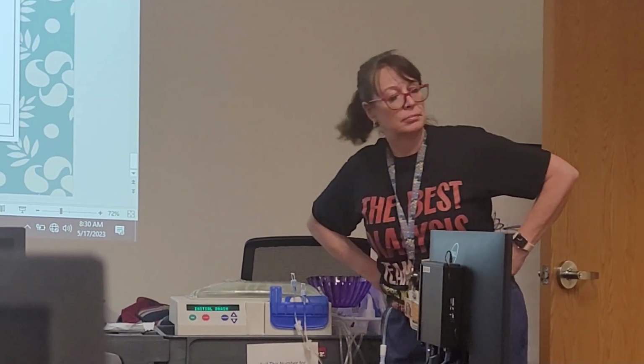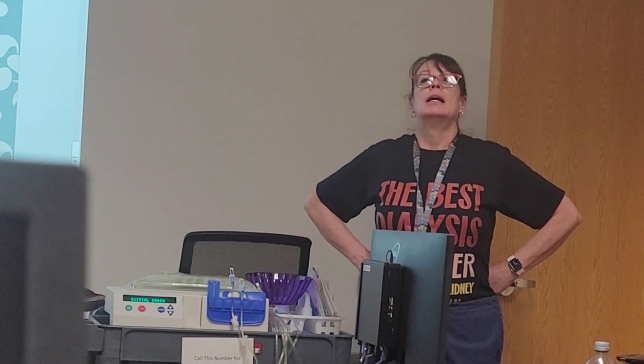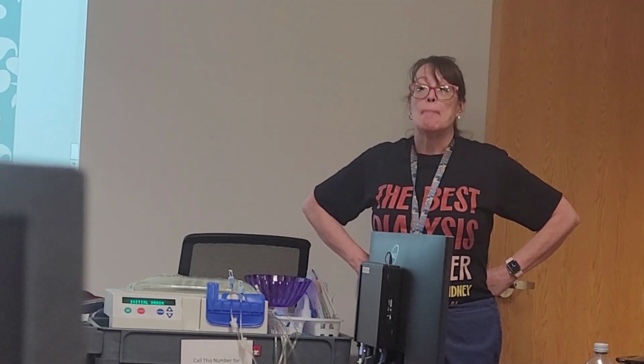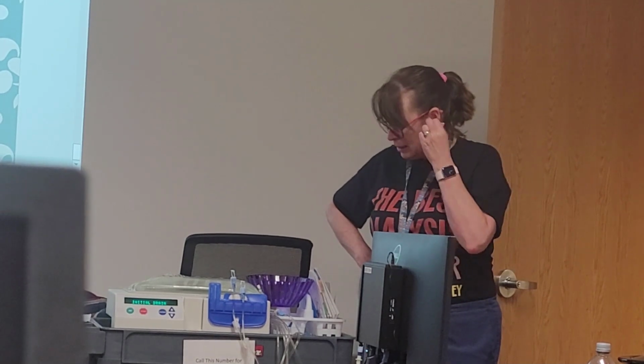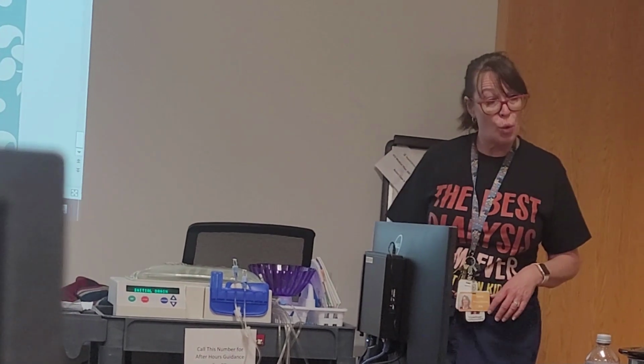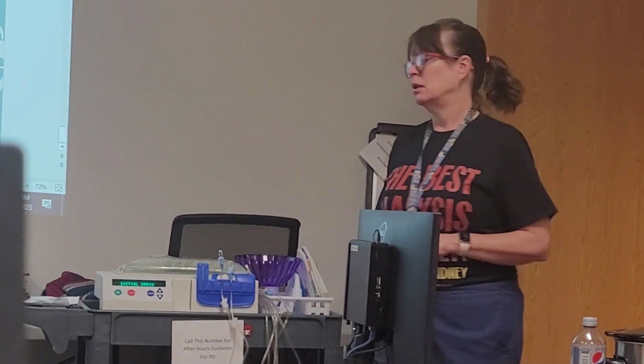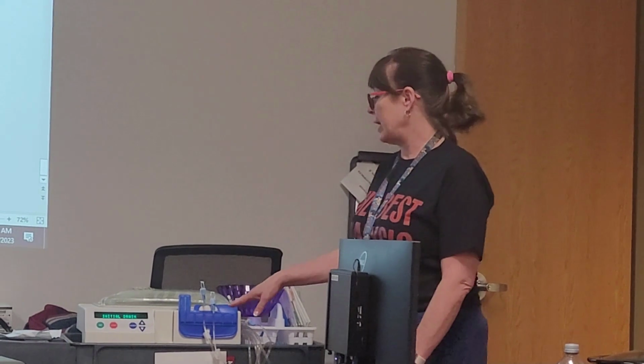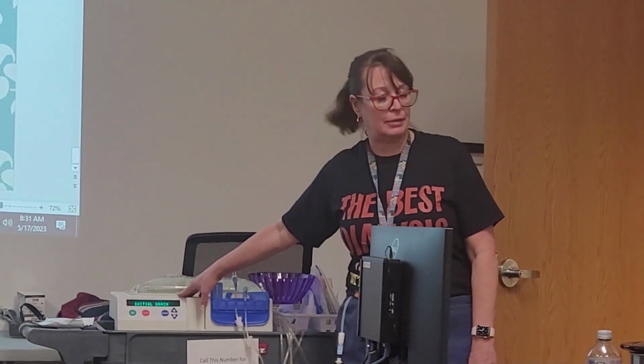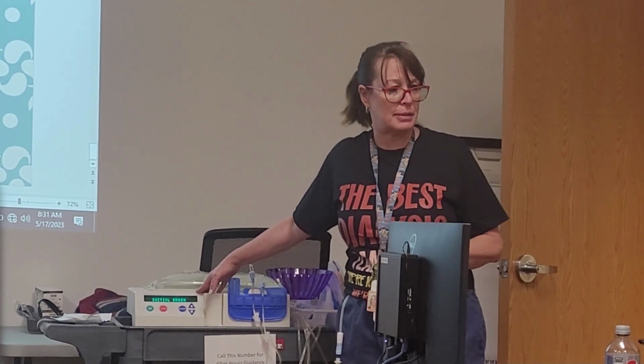So we recently had a patient who does PD at home and said that, typically at the onset, she has issues with the initial drain and her home machine is able to bypass it. And what I learned from Baxter was that we cannot do that on these machines. We can, okay, but there's a special set of circumstances. My general rule of thumb is that if it initial drain alarms 3 times, and we know for a fact that there's nothing else in there, then it has to actually be alarming for us to bypass it. So if I go in and it's an initial drain, I can't bypass that right now. It has to be actively alarming for me to be able to bypass that.